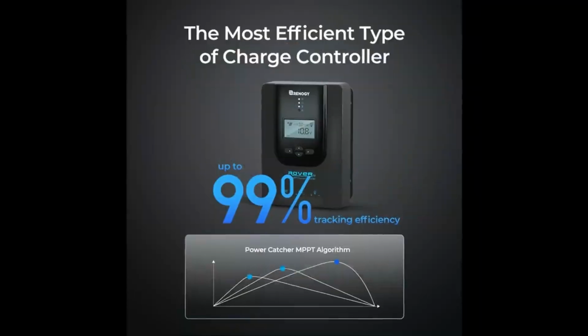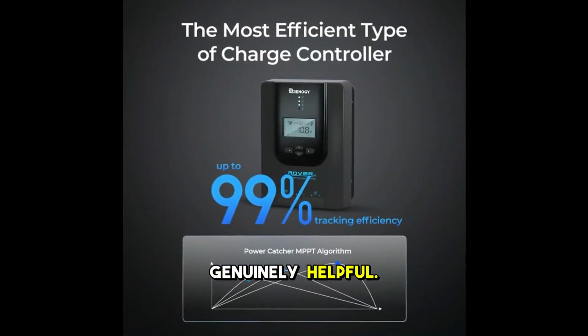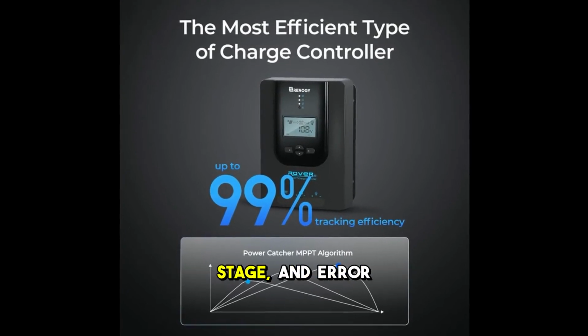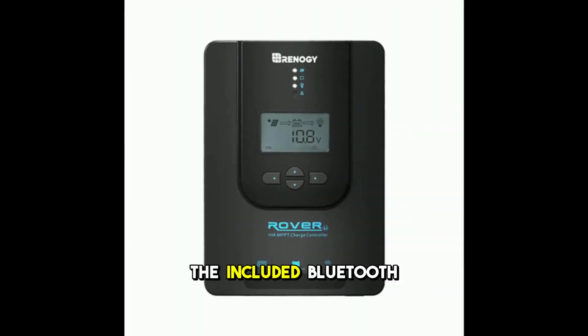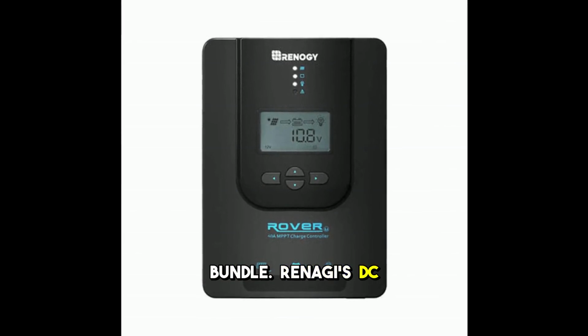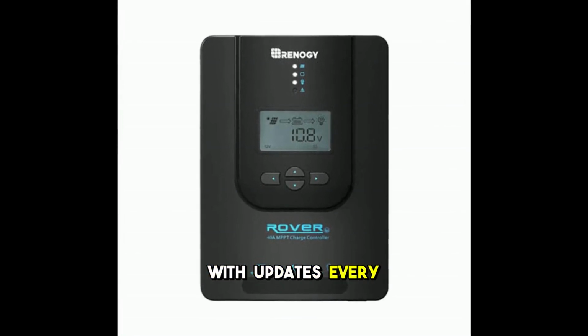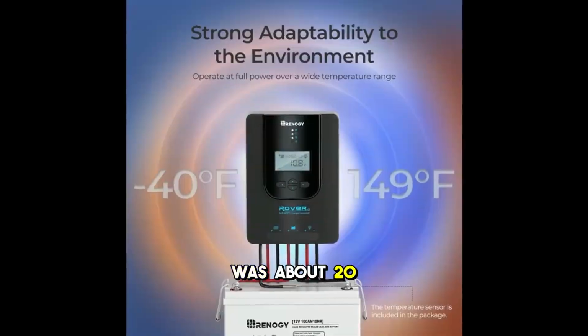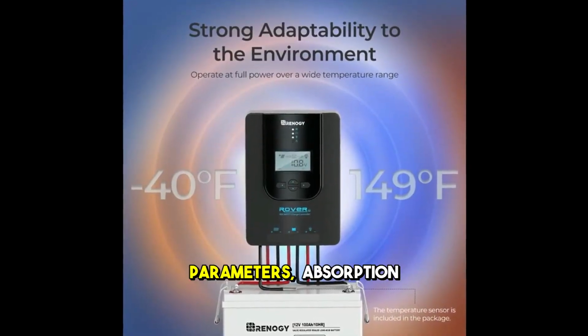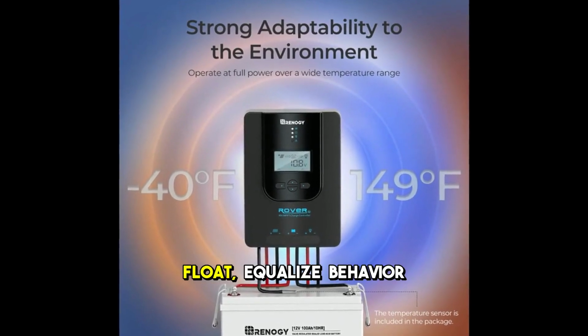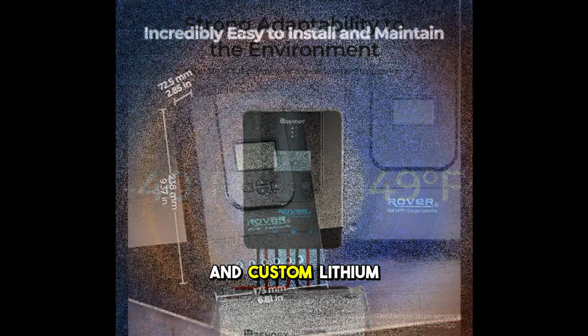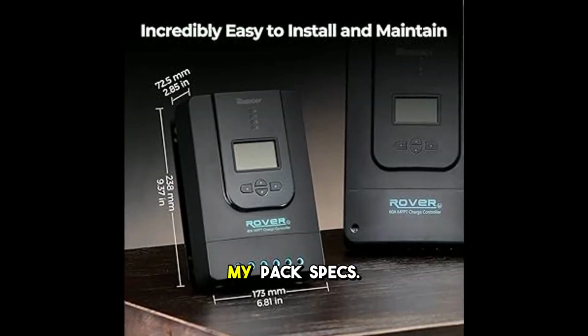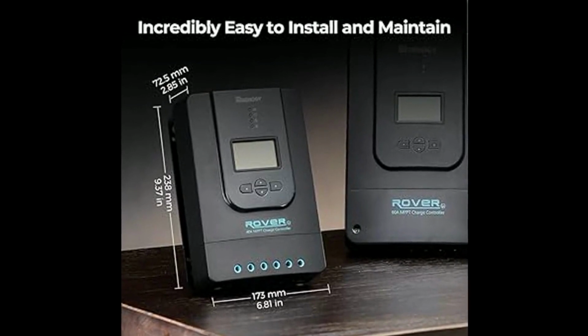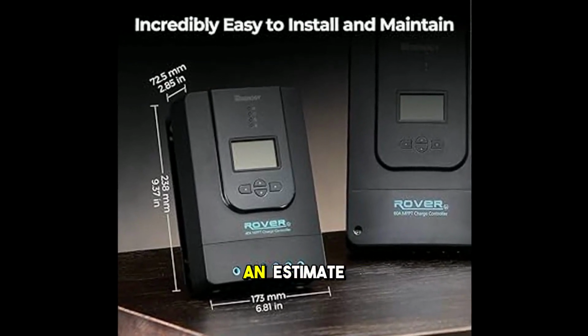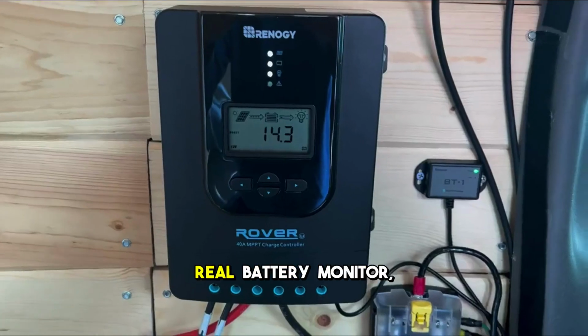And the day-to-day stuff, the LCD is genuinely helpful. Voltages, currents, charge stage, and error codes you can actually interpret. The RJ45 port let me use the included Bluetooth module in my bundle. Renogy's DC Home app gave me live data with updates every few seconds. Range was about 20 to 25 feet. I could edit key parameters, absorption voltage and time, float, equalize behavior on lead acid, and custom lithium settings in user mode to match my pack specs. It's clear though, the app is not a shunt. Amp hour math is an estimate. If you want true state of charge, add a real battery monitor.